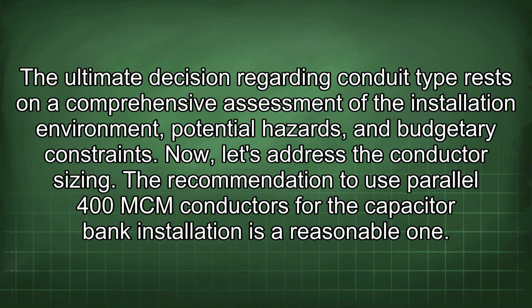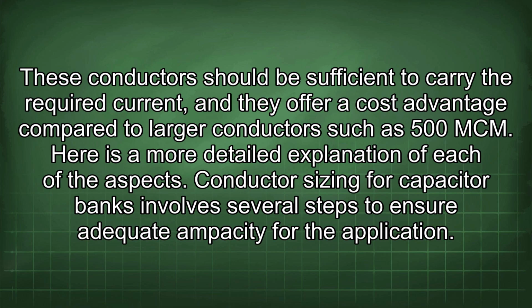Now let's address the conductor sizing. The recommendation to use parallel 400 MCM conductors for the capacitor bank installation is a reasonable one. These conductors should be sufficient to carry the required current, and they offer a cost advantage compared to larger conductors such as 500 MCM. Here is a more detailed explanation of each of the aspects.